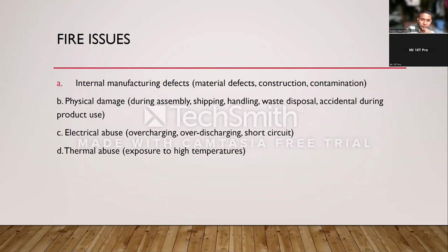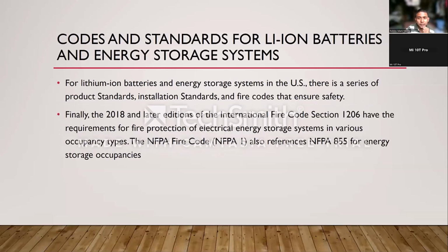Sa electrical abuse, syempre overcharging yan. Tsaka yung mga short circuit, overload. Thermal abuse is exposure to high temperature. Codes and standards for lithium-ion batteries and energy storage systems. For lithium batteries, energy storage, series of product standards, installation standards. And later, the 2018 International Fire Code Section 1206 requires the protection of electrical energy storage systems. The NFPA Fire Code also references NFPA 855 for energy storage occupancies.